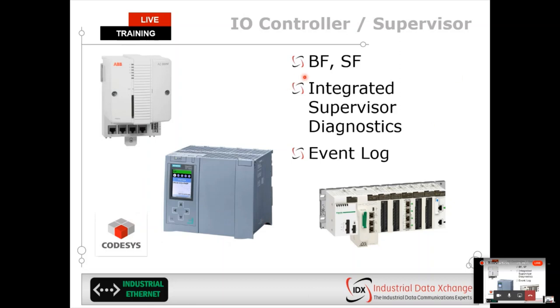Firstly, these controllers would have two LEDs called BF and SF. SF means there's something wrong with myself — my configuration, a system fault. BF, bus fault, means there's some error in my industrial communication network that needs to be addressed. If you go into the integrated supervisor diagnostics, log into the device with the relevant software, or even, for example, the Rockwell PLCs have an integrated web page giving you useful statistics on the Ethernet IP network that can help identify errors in the Ethernet IP configuration.